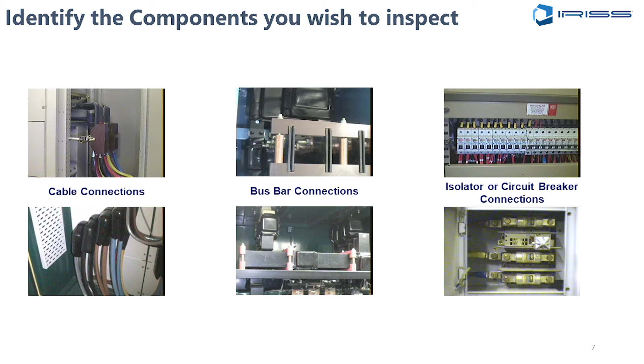Now, if I have an electrical connection and I perform infrared and don't see anything unusual temperature-wise, and I listen with my ultrasound test equipment and don't hear anything unusual, and it's medium voltage so I hook up transient earth voltage detection to look for partial discharges, and there's nothing there. I run motor current analysis on the motor connection, and everything looks fine, within normal parameters. I do a UV scan overhead, everything's good. I visually inspect it, it's clean, no water, no pests, nothing going on, and I don't smell anything funny.